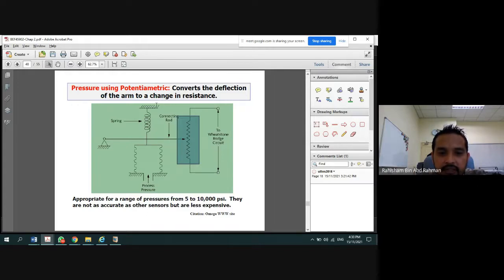The movement of this connecting rod, as you can see here, will change the potentiometer. When the potentiometer changes, the resistance value changes, and this is directly reflected in the circuit, I mean the voltage level. Once the resistance value changes, the voltage can easily be found if we use a Wheatstone bridge circuit. They are not accurate, but this one is appropriate from 5 to 10,000 psi. It depends. It is very simple and less expensive, but not accurate, as I mentioned, because we are talking about a very wide range, up to 100,000 psi.